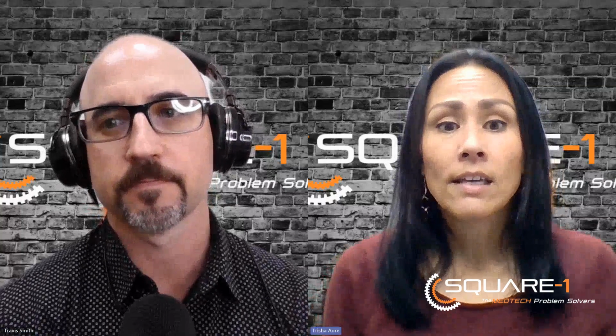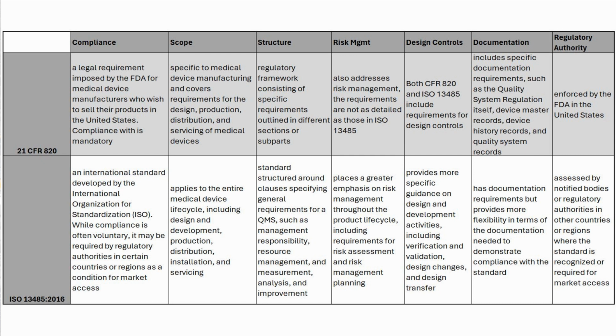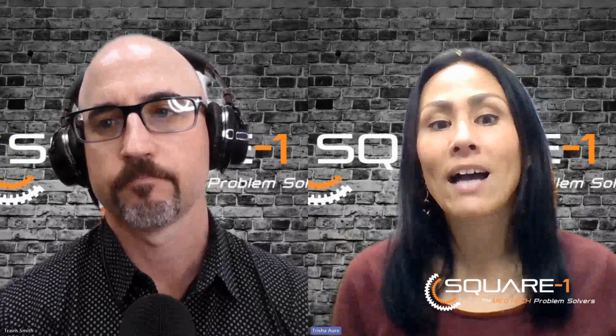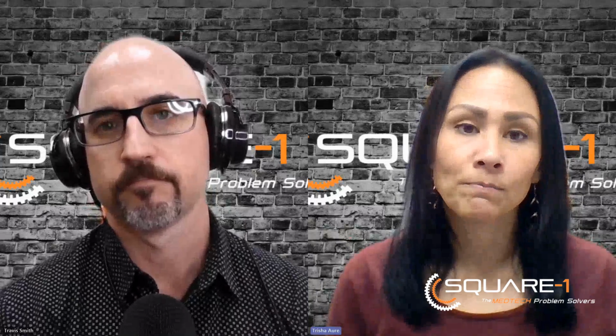Absolutely. Another key area to really look at is, yes, the CFR 820 has risk management involved, but with 13485, there's a greater emphasis on risk management, and that's including the risk assessment and risk management planning. For example, on the planning side, we would be looking at analyzing risk's likelihood and impact, developing strategies to minimize harm and monitoring their effectiveness.